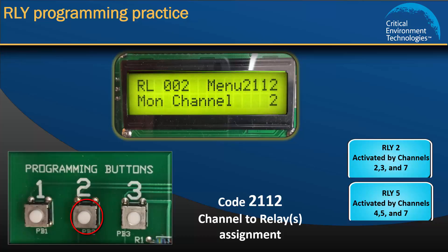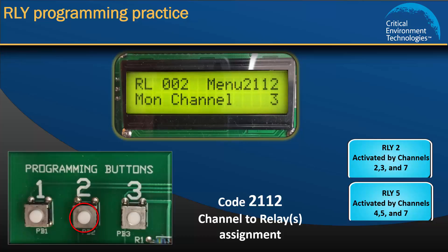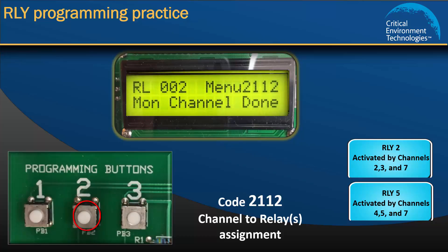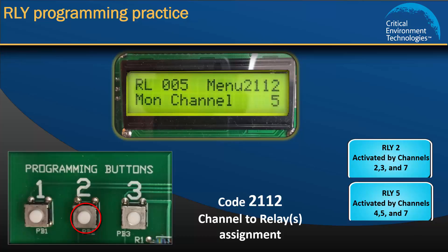Press 2 again to move on to Relay 2. We want Relay 2 to be activated by Channels 2, 3, and 7. The display should show Relay 2, Channel 2. Press 2 to save and the display will show "Mon Channel done." Press 3 to increase the Mon Channel number to 3 and press 2 to save. Press 3 to increase the Mon Channel number to 7 and press 2 to save. The display will show "Mon Channel done." Now we have assigned Channels 2, 3, and 7 to Relay 2. Press 2 again to move on to Relay 3, again to Relay 4, and once more to Relay 5. Stop at Relay 5.